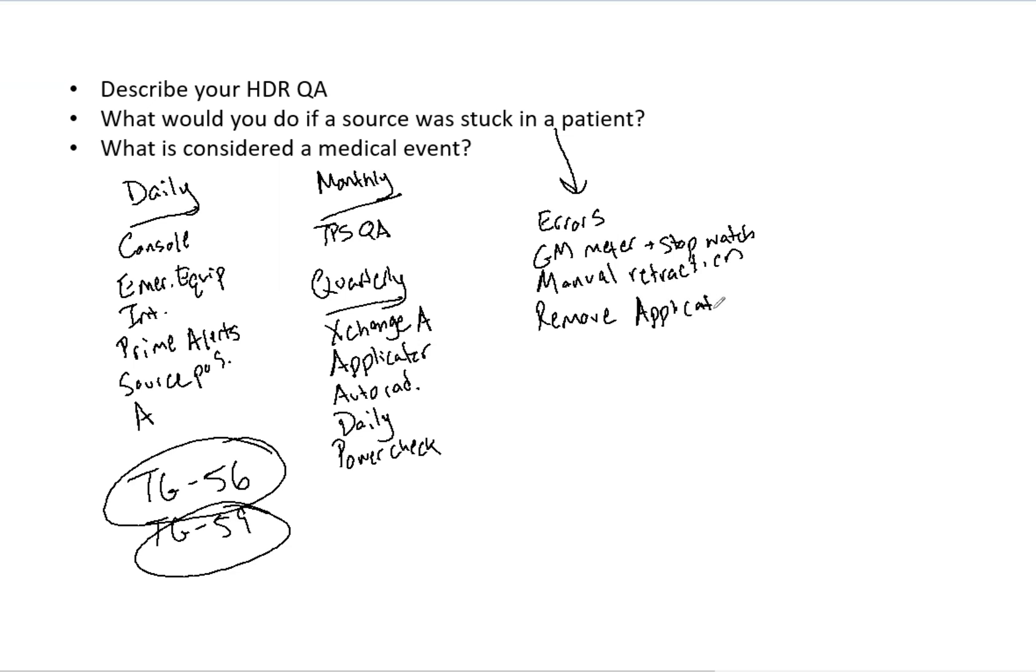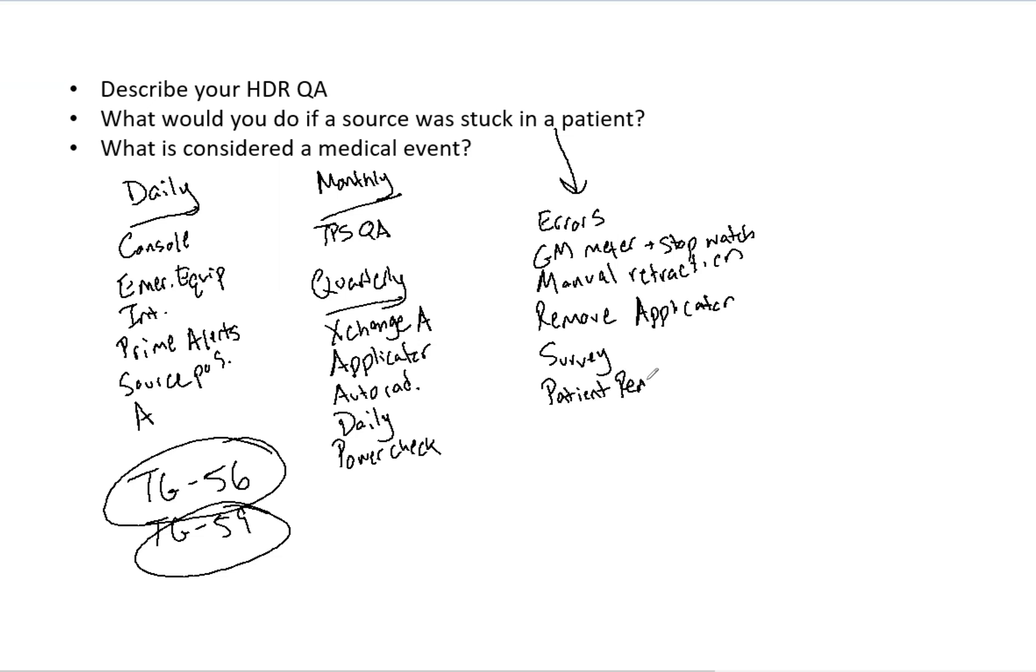And so beforehand, you should talk with your clinic about this. Is a nurse going to remove the applicator? Is the physician going to remove the applicator? And then once that is done, you want to survey the patient and the equipment, and then you want to remove the patient from the room. Again, you want to survey because you want to verify the source is no longer in the patient. It should be either ideally in the HDR unit.